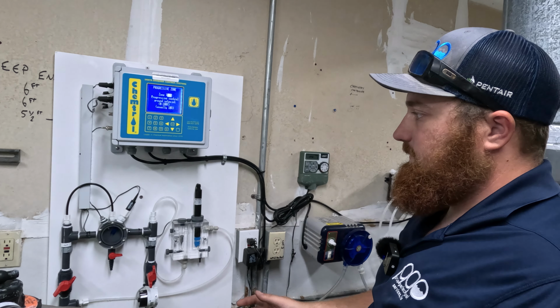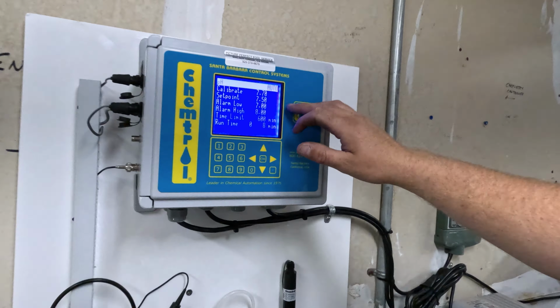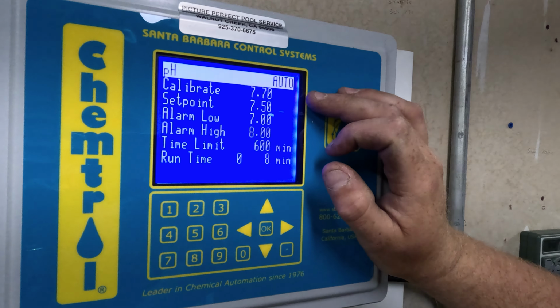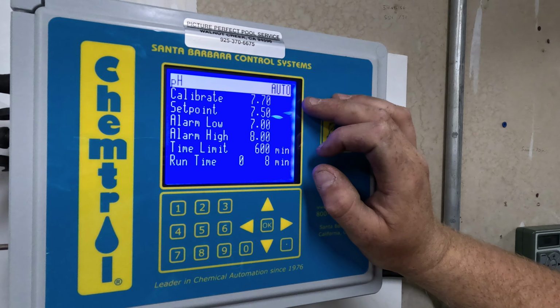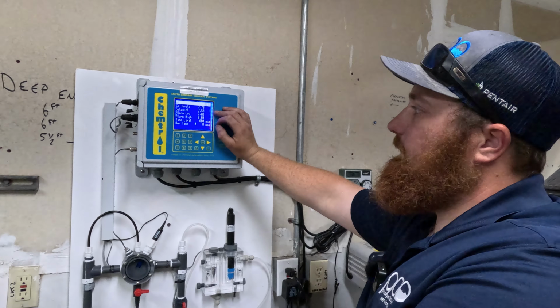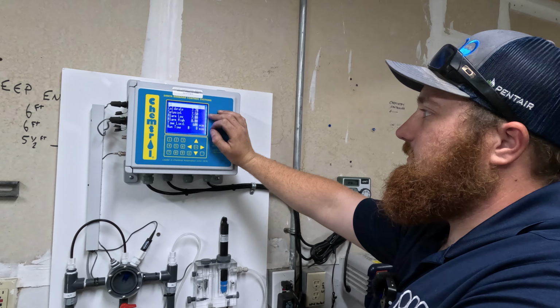So this is the distance. It's 5% from the set point that it's going to do that pulse feeding action. Since this is such a large body of water, we're not really worried about overshooting. We're just going to leave it at 5%. Hit OK. So our calibration is 7.7. New controller. Our set point is 7.5. That's where we're going to keep it in this case.